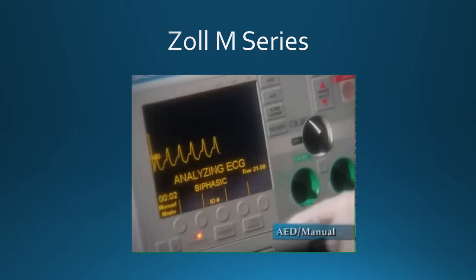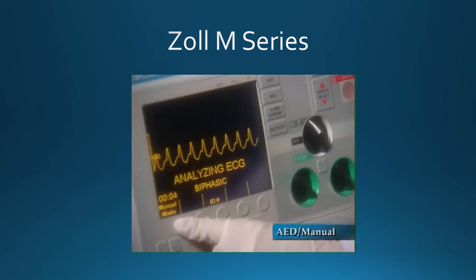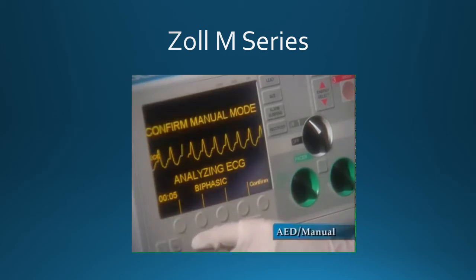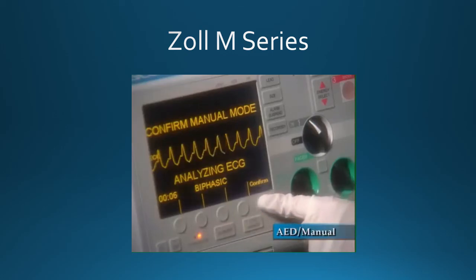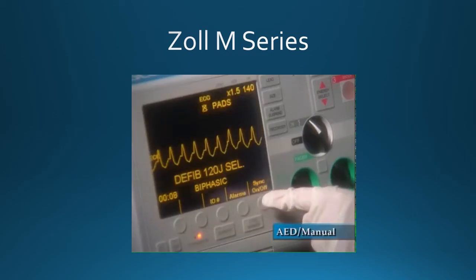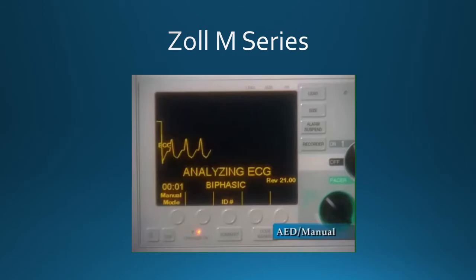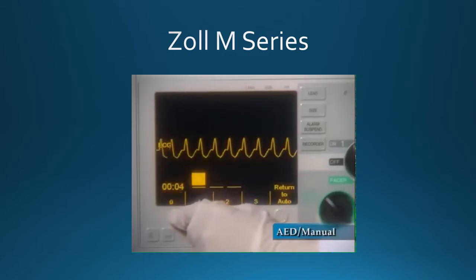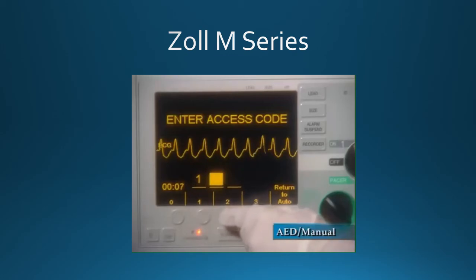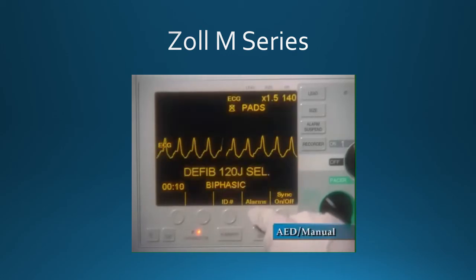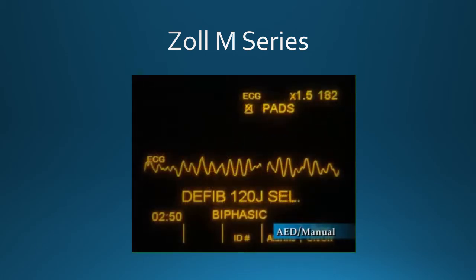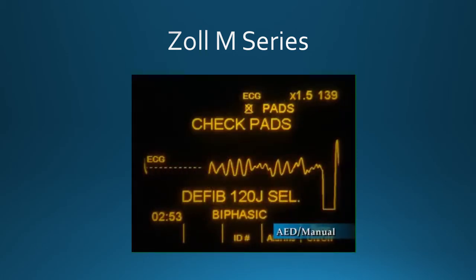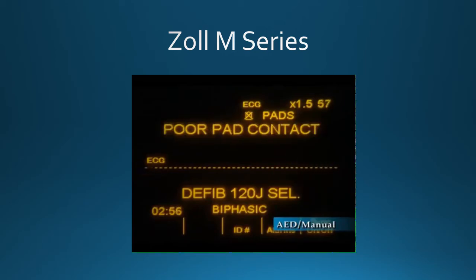Press the Manual Mode soft key on the front panel of the unit to enter the manual mode of operation. If the Confirm soft key is not pressed within 5 seconds, the unit will revert to semi-automatic operation. If the M-Series has been configured to require an access code, Enter Access Code will be displayed, and the operator will have to enter a 3-digit access code by pressing the soft keys corresponding to the correct digits. If the MFE pads are not making good contact, or if a short circuit between the pads exists, 2 messages, Check Pads and Poor Pad Contact, will be alternately displayed, and energy will not be delivered.